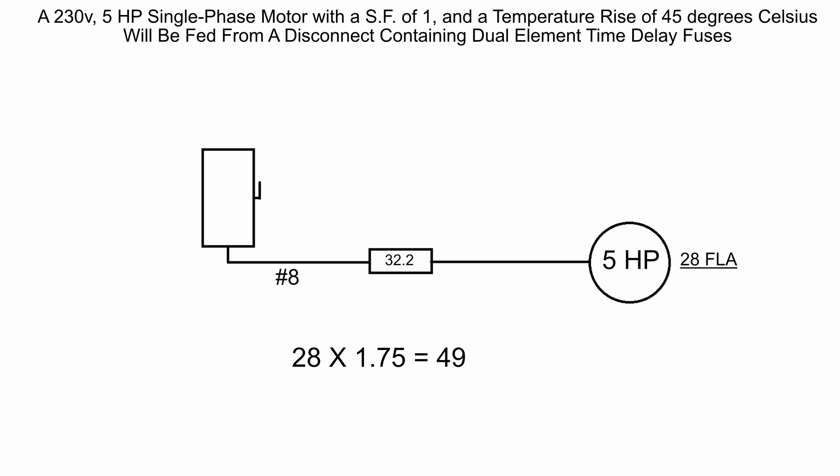Since this is a branch circuit on a motor and not a feeder supplying or an overcurrent device protecting multiple motors, we can go up to the next standard size for simply one single motor and that will take us up to 50 amps for the overcurrent protective device. That is how you size a motor, its branch circuit, its thermal overloads, and its overcurrent protective device.